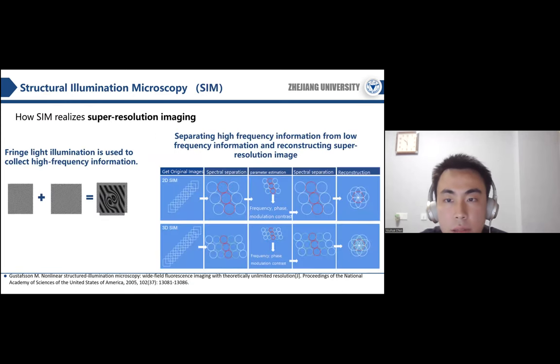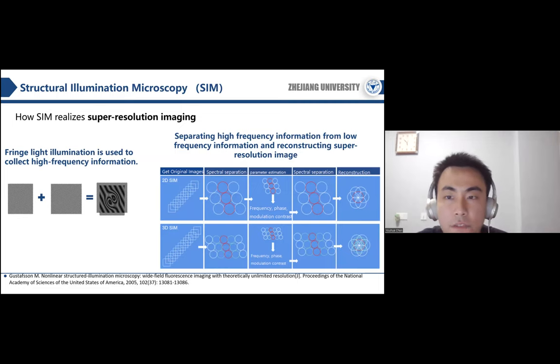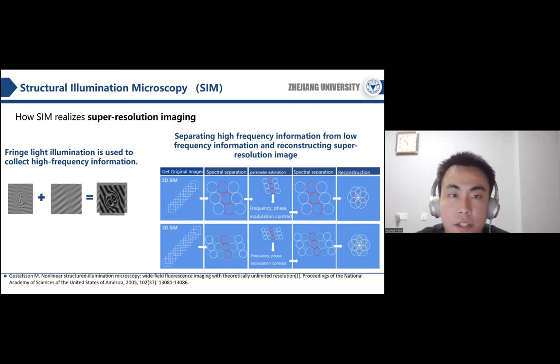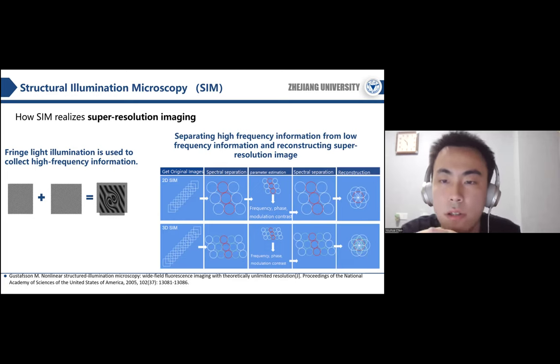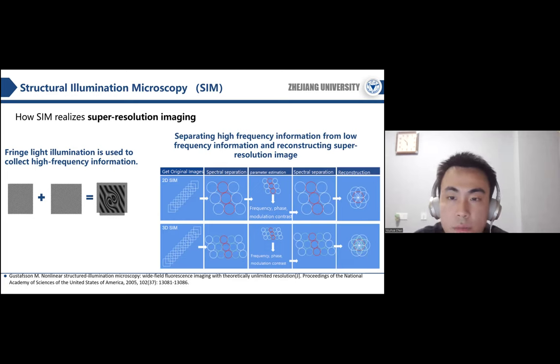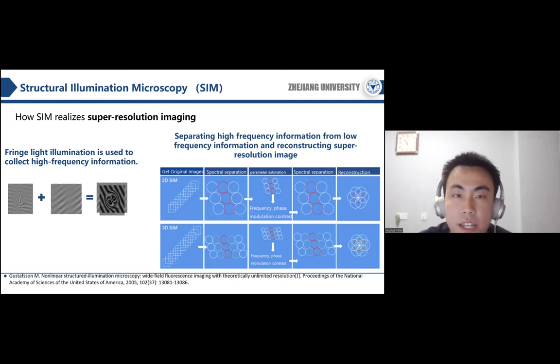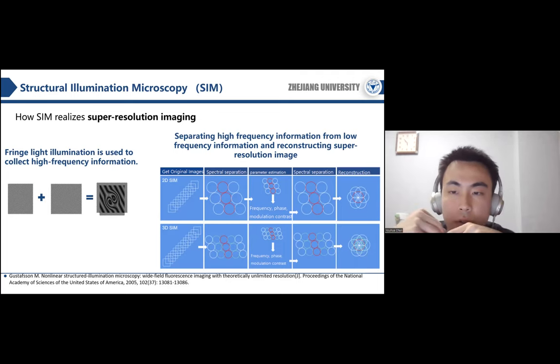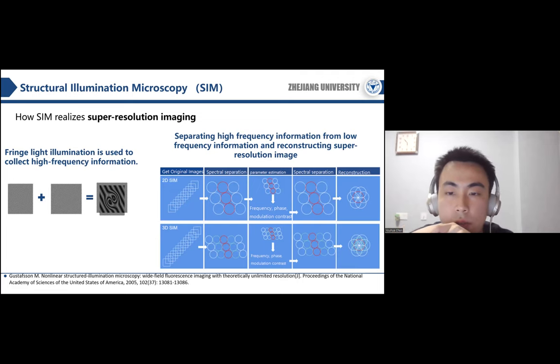SIM is based on a common optical illusion known as the Moiré effect. When two high-frequency patterns are superimposed on each other, low-frequency Moiré fringes will be generated. By illuminating the sample with fringe light with a cosine structure, it is possible to collect high-frequency information in the form of low-resolution Moiré fringes, which are not available due to lens aperture limitations. The high-frequency information is then separated from the low-frequency information through post-processing to reconstruct the super-resolution image.